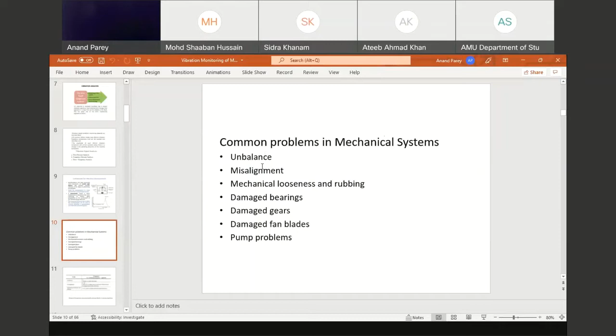Once you capture the vibration signal, you have to find its frequencies, because there is a relation between frequency and any fault that is going to develop. For unbalance, if in the frequency domain the rotational frequency component is quite high, mainly in the radial direction, you can conclude that some unbalance has developed, and that has to be rectified.